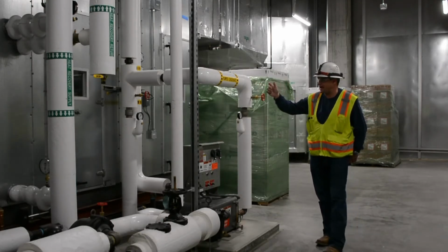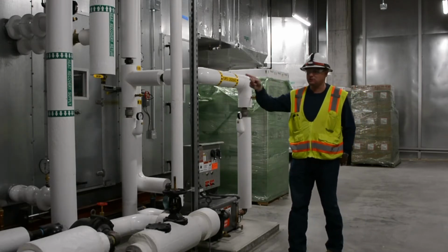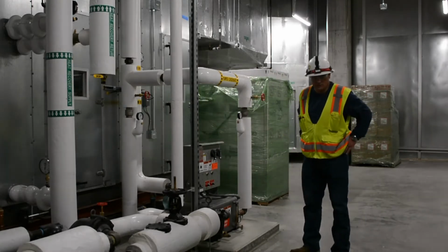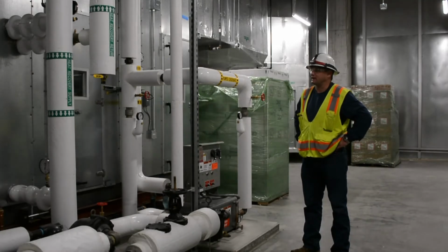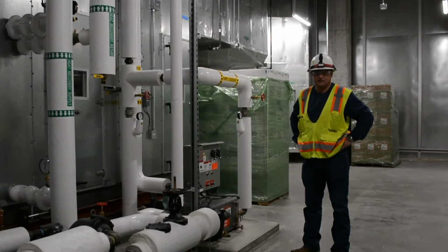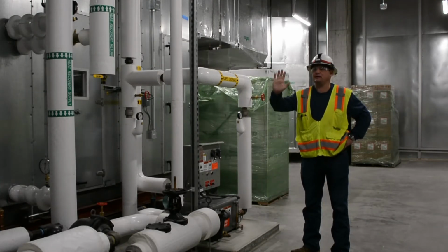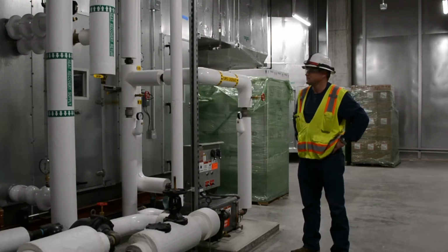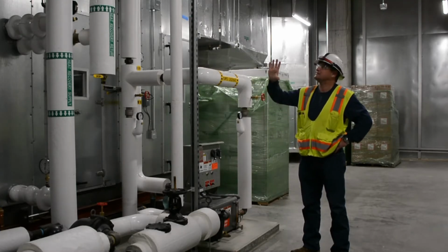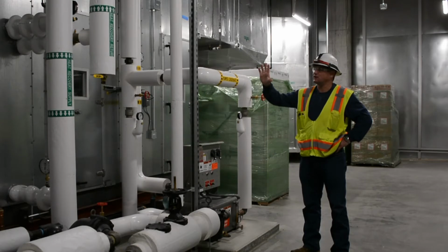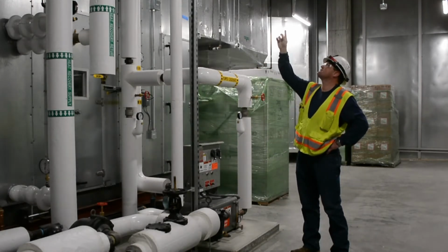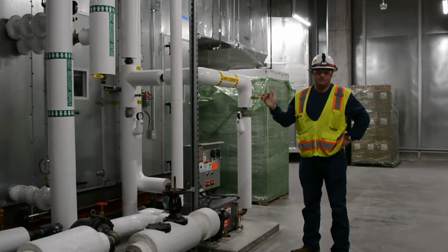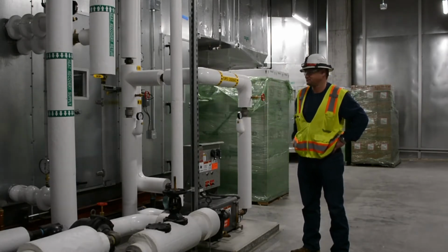This section also has our first coil, which is the heat recovery coil. That coil has a glycol loop connected to it, so that is pre-treating the outside air for the ability for our other components for preheat and chilled water to not work as hard. There's no maintenance or anything required of this coil other than just making sure that the operations of the three-way valve are 100% open whenever the system is enabled.